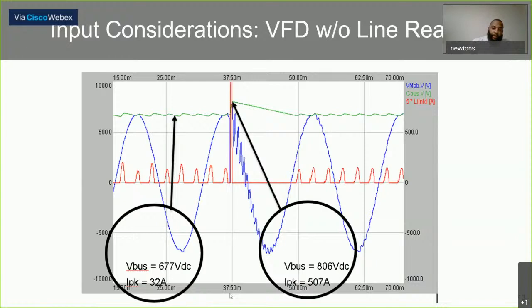So what happens? Where do you see the change? Over here on the x-axis, you'll see at 37.50 milliseconds, a capacitor bank was closed, thus causing a disturbance on your line side of your VFD. Well, what type of disturbance did we see? Before this cap bank closed, our DC bus voltage was floating at 677 volts DC, and our peak current was floating at 32 amps.